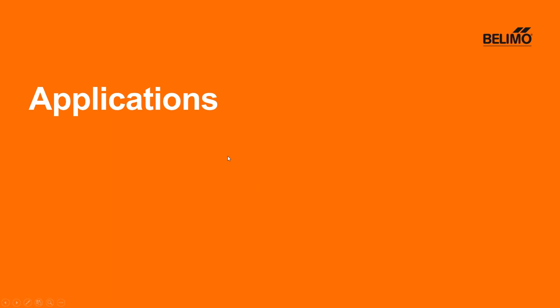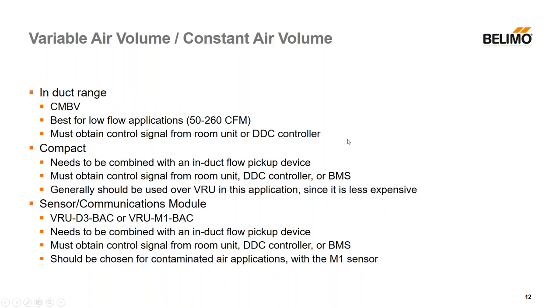Now I've given an overview of the products — let me touch on some of the applications where you'll most likely see them. Probably the most common application is either variable air volume or constant air volume. Starting with the induct range, which is the smallest of the three, we have the CMBV range, best for low flow applications — around 50 to 260 CFM. An important thing to note is that it needs to obtain the control signal from a room unit or DDC controller; even though it can sense duct flow, it still needs a set point from something else.